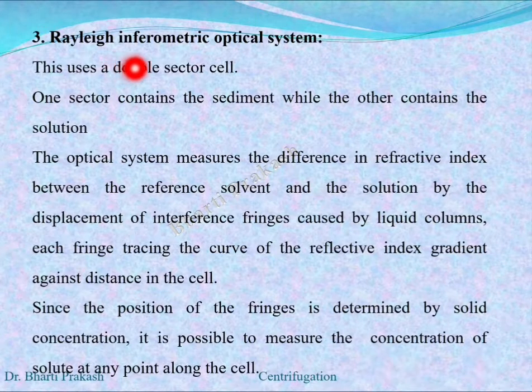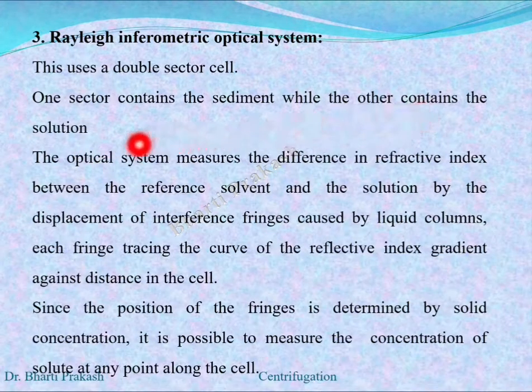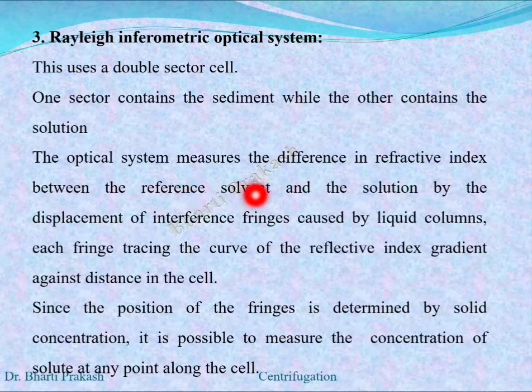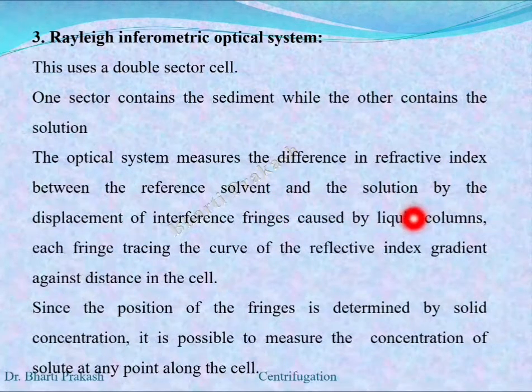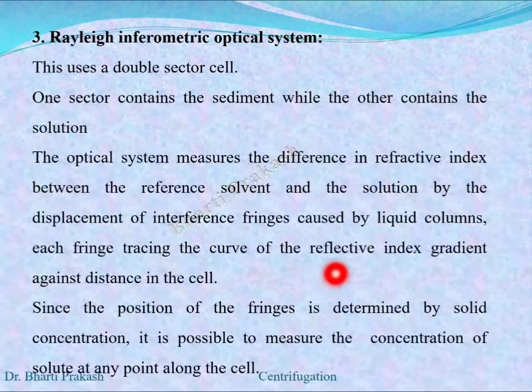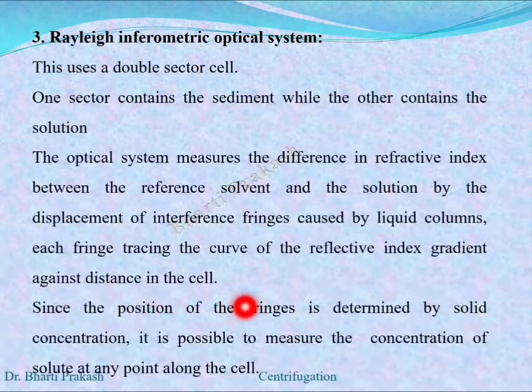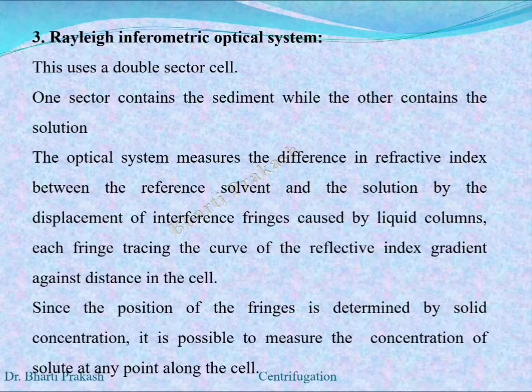The Rayleigh interferometric optical system uses a double sector cell — one sector contains the sediment while the other contains the solution. The optical system measures the difference in the refractive index between the reference solvent and the solution by the displacement of interference fringes caused by liquid columns. Each fringe traces the curve of the refractive index gradient against distance in the cell. Since the position of the fringes is determined by the solute concentration, it is possible to measure the concentration of solute at any point along the cell.